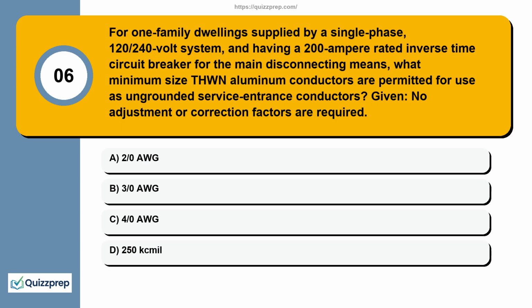Question 6. For one-family dwellings supplied by a single-phase, 120/240-volt system, and having a 200 ampere rated inverse time circuit breaker for the main disconnecting means, what minimum size THWN aluminum conductors are permitted for use as ungrounded service entrance conductors? Given, no adjustment or correction factors are required. 2/0 AWG, 3/0 AWG, 4/0 AWG, 250 kcmil.